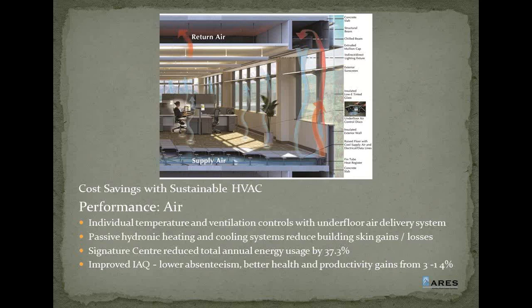and both systems are underfloor delivery. So we have underfloor air delivery for the core of the building, and at the perimeter, 5 feet of the building, we looked at that as a completely separate zone, taking care of just the skin load of the building, and we did that with hydronic, both hot water in the baseboard and cold water above in a system called chilled beams. We use the passive nature of the hydronic instead of having fans to control that, it's simply controlled by natural ventilation. Hot air rises, cold air falls, capture hot air, it pressurizes the space, forces the cold air to fall. It's a pretty controlled system.